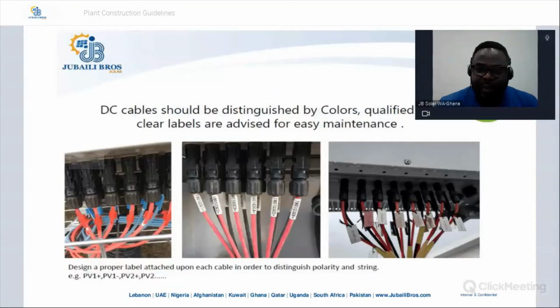Absolutely crucial. Again, things we don't expect you to do: if you are cabling, remember the Huawei systems require you to terminate directly onto the inverter. So this is maybe string 1, string 2, string 3, string 4, string 5, string 6 - if you're terminating them, please put some color coding. It is absolutely important, especially if you are not going to be the same person doing the O&M for this system. We all know black is always negative, red is positive, or any other two different colors you can use.